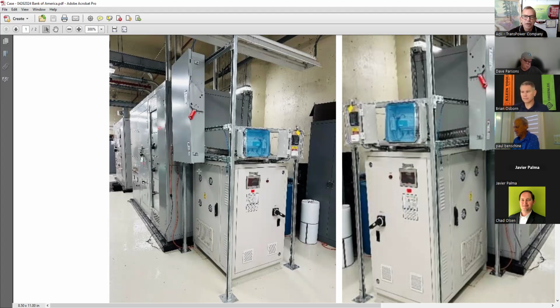So we started this job at 4 o'clock in the morning. We met there, and by 5 o'clock went over the checklist steps. We had to go up every floor to turn the sub panel off, then turned the switch gear off, the main switch. Then the utility arrived outside at 6 o'clock.